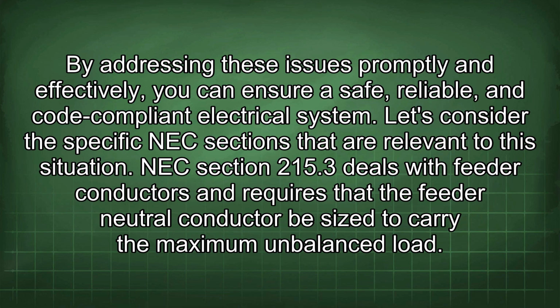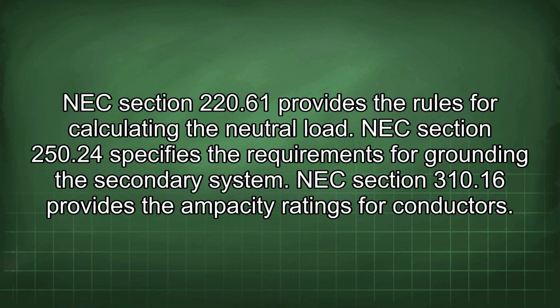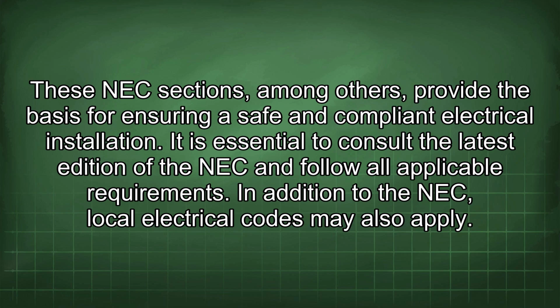Let's consider the specific NEC sections that are relevant to this situation. NEC Section 215.3 deals with feeder conductors and requires that the feeder neutral conductor be sized to carry the maximum unbalanced load. NEC Section 220.61 provides the rules for calculating the neutral load. NEC Section 250.24 specifies the requirements for grounding the secondary system. NEC Section 310.16 provides the ampacity ratings for conductors. These NEC sections, among others, provide the basis for ensuring a safe and compliant electrical installation. It is essential to consult the latest edition of the NEC and follow all applicable requirements.